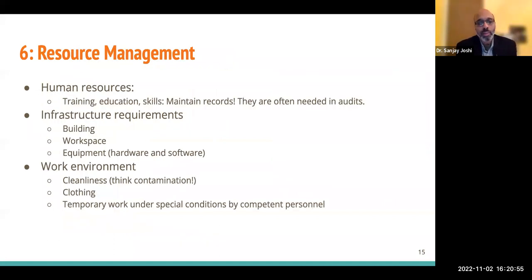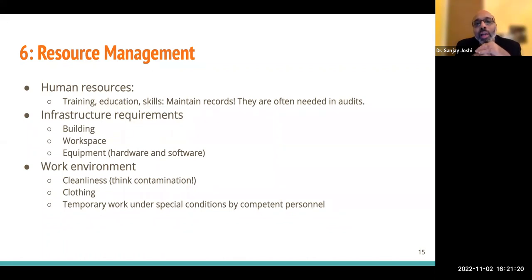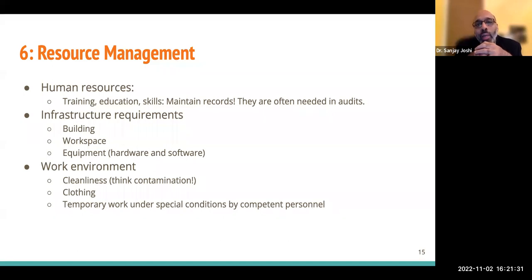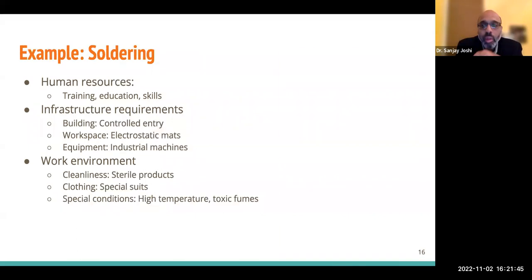Section 6 is resource management. On human resources, the standard wants you to look at training, education, and skills. In almost every audit I have been in, anytime they see a person doing something, the auditors ask to see the training record for that person — this is super important. If somebody is doing something, are they trained for it? There are also infrastructure requirements — requirements on your building, workspace, equipment (hardware or software), work environment including cleanliness and clothing. There may be situations when somebody who is trained needs to work under special conditions. We'll take a look at an example of soldering.